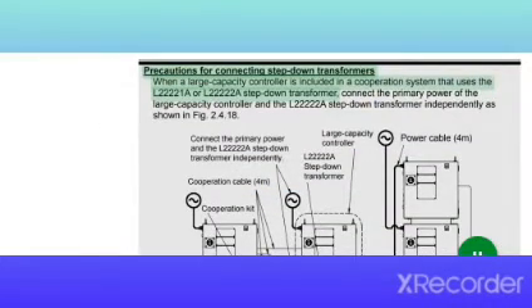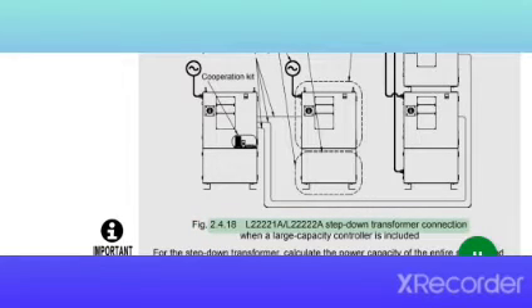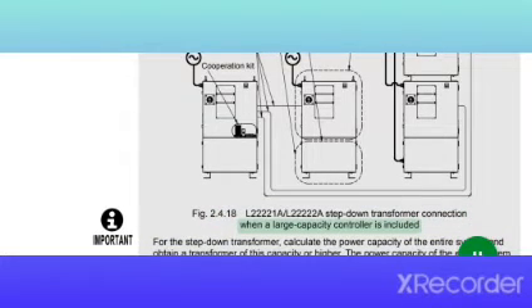Important. Precautions for connecting step-down transformers when a large capacity controller is included in a cooperation system that uses the L22221A or L22222A step-down transformer. Connect the primary power of the large capacity controller and the L22222A step-down transformer independently as shown in Fig. 2.4.18. Power cable 4 meters M. Large capacity controller. Connect the primary power and the L22222A step-down transformer independently. L22222A. Step-down transformer. Cooperation kit. Cooperation cable 4 meters M. Fig. 2.4.18 L22221A/L22222A step-down transformer connection. When a large capacity controller is included.